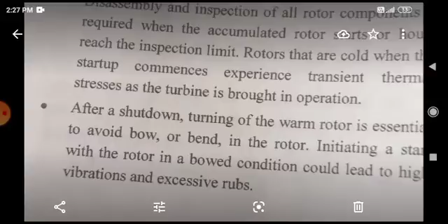Okay, then rotor parts. Disassembly and inspection of all rotor components is required when the accumulated rotor starts or hours reach the inspection limit. Rotors that are cold when the startup commences experience transient thermal stresses as the turbine is brought into operation. After a shutdown, turning of the warm rotor is essential to avoid bow or bend in the rotor. Initiating a start with the rotor in a bowed condition could lead to high vibrations and excessive rubs.